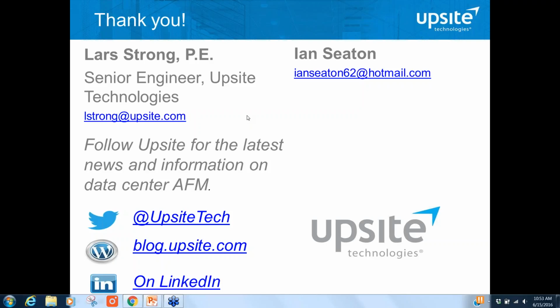Okay. Yeah, this is Lars, and I've had a number of people push back on that concept as well. However, the point at which the returns start to diminish by raising temperatures is generally higher than most people realize, or certainly higher than most people are operating at. Yeah, it has to do with that class of server. But generally, it's with the intake temperatures, the average intake temperatures, and ideally consistent intake temperatures being somewhere in the high 70s. And it's still very uncommon for data centers to be operating with IT equipment intake temperatures consistently, and evenly in the high 70s. There's usually quite a bit of room to go. Okay, thank you for that.